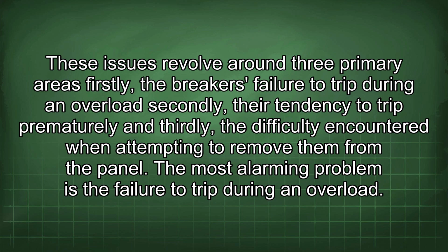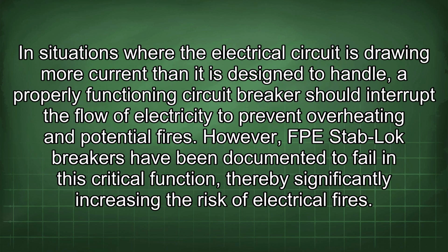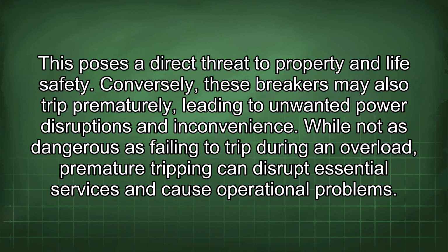The most alarming problem is the failure to trip during an overload. In situations where the electrical circuit is drawing more current than it is designed to handle, a properly functioning circuit breaker should interrupt the flow of electricity to prevent overheating and potential fires. However, FPE Stab-Lok breakers have been documented to fail in this critical function, thereby significantly increasing the risk of electrical fires. This poses a direct threat to property and life safety.